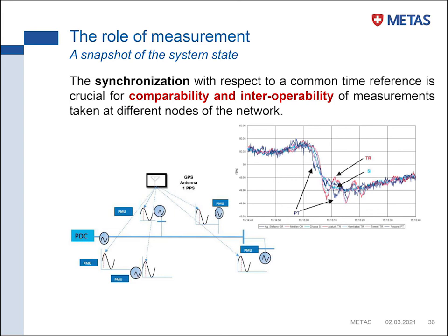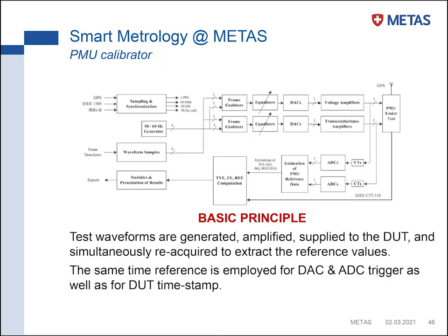Another question is, do you consider remote calibration of PMUs deployed in the network, or do the PMUs have to come to METAS to be calibrated? For calibration, I think you can do remote calibration periodically. At least what I've seen at NIST is the center for PMU calibration. Before deploying in the field, a device among the set of devices is calibrated in the lab with all the tests, and then they do some periodical checks. Obviously you cannot reproduce all the tests in the field, but you can do some statistical analysis.